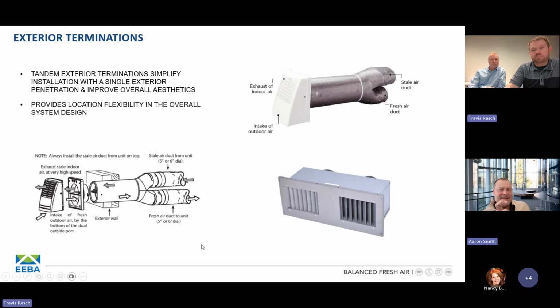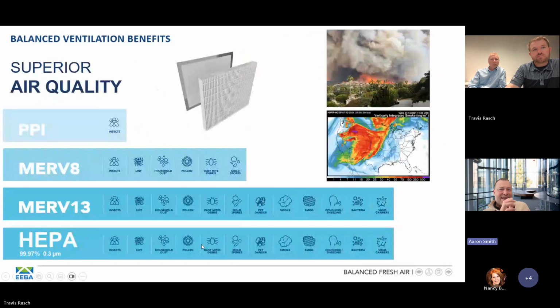I had one question on your HEPA versus MERV 13 slide, Travis. So when I looked at that, I read it that MERV 13 is equal to HEPA. I know it's two different languages, but I think I had always heard that actually MERV 16 was a little bit more equivalent to HEPA. So was I reading this chart incorrectly? Not necessarily incorrectly, it's the efficiency in which that particle matter is captured. So HEPA is its effectiveness to capture that 99.9% efficient compared to a MERV 13.